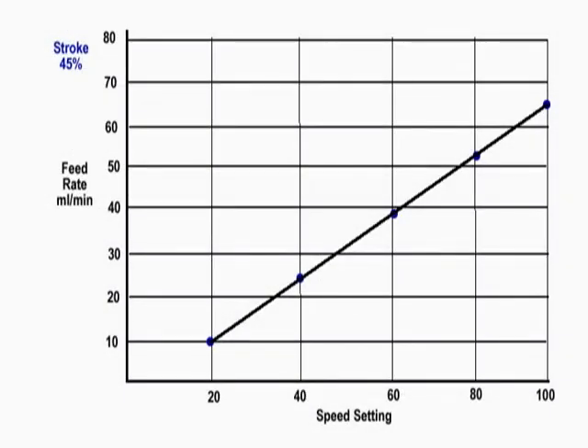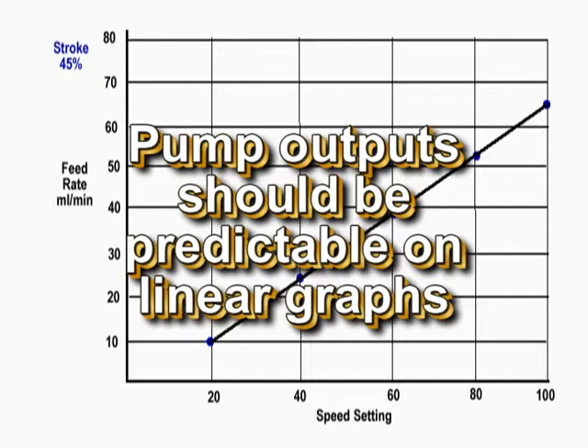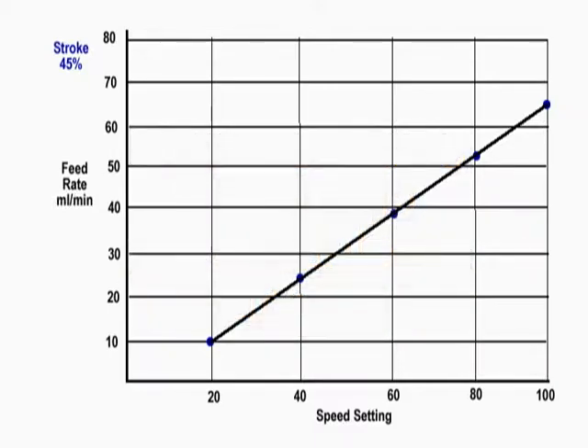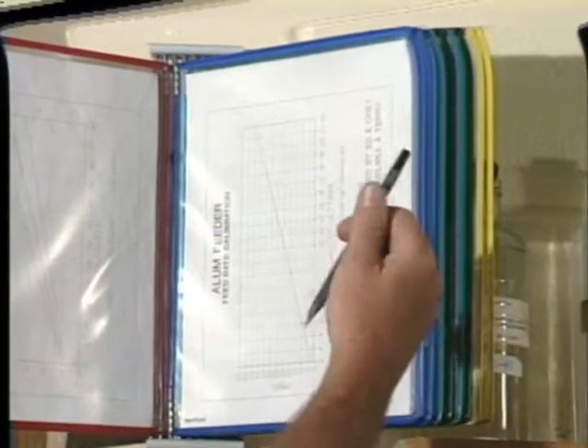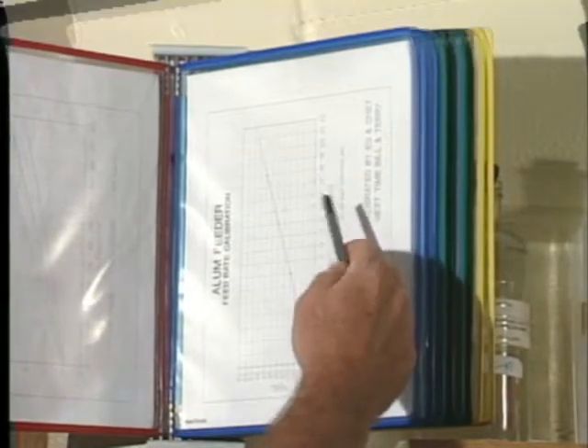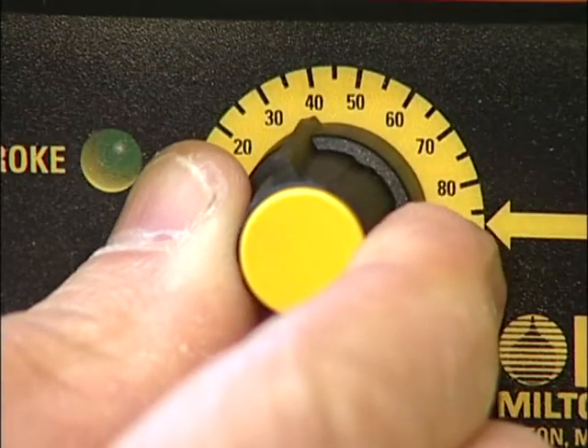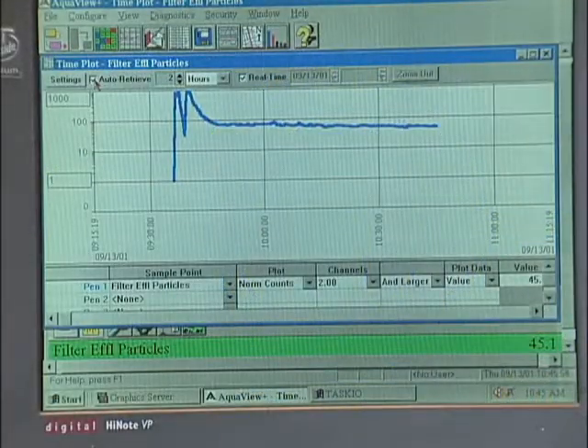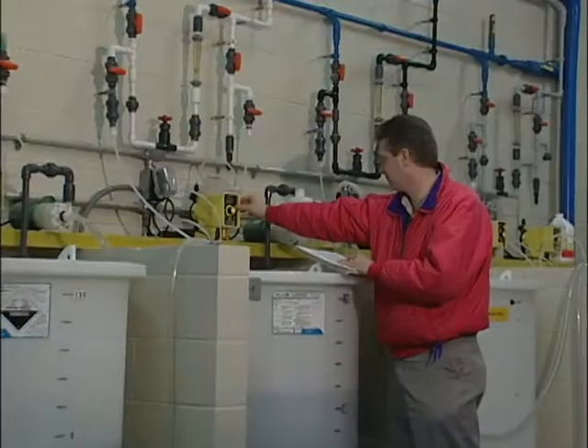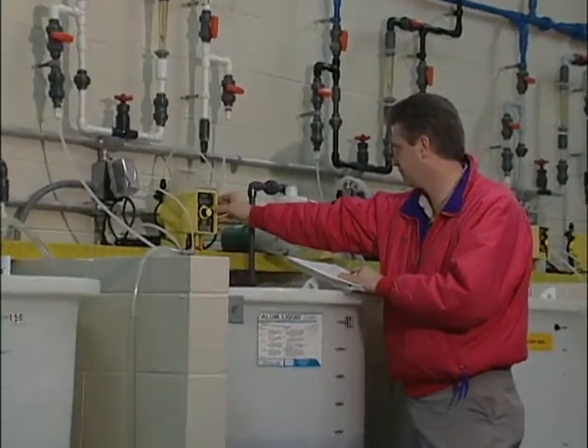Operators should be able to predict reasonably well what the delivery will be at settings within the ranges established by the graph. This information should be kept near the pump in a waterproof container so it can be easily referenced when adjustments are required. Coupling this information with historical records from past events will enable the operator to make accurate adjustments of chemical feeds in response to changing water quality characteristics.